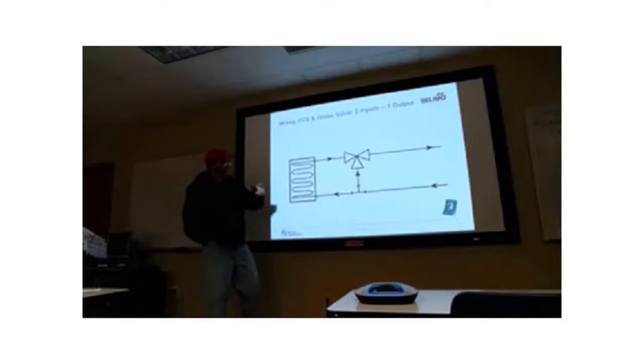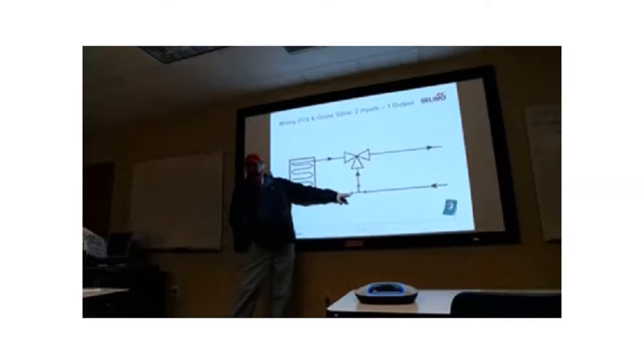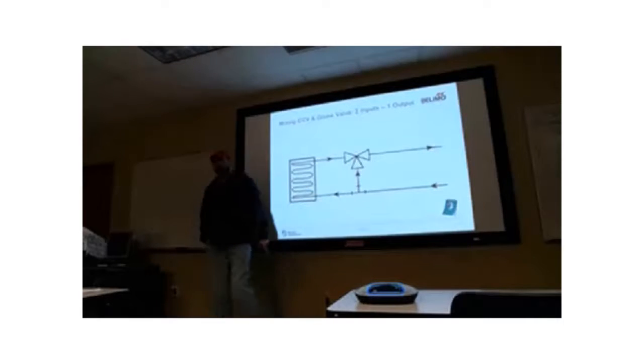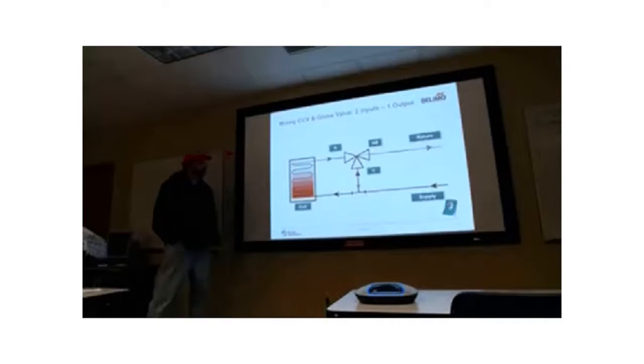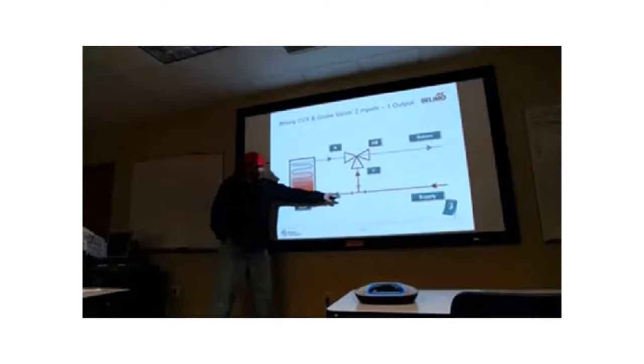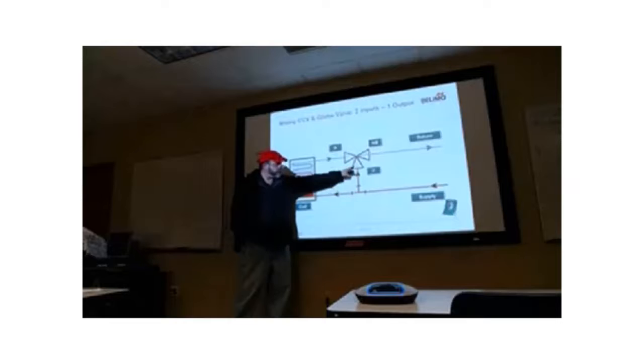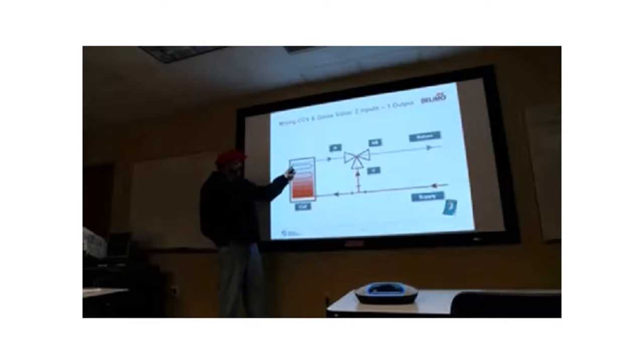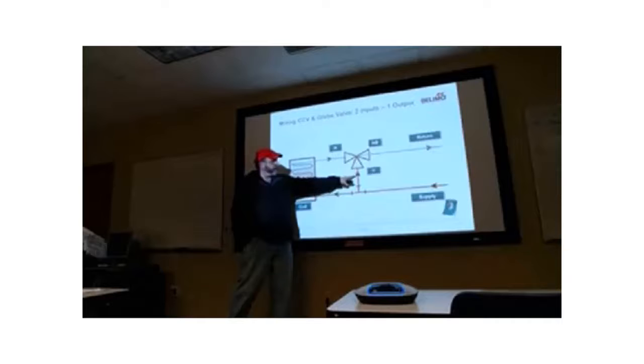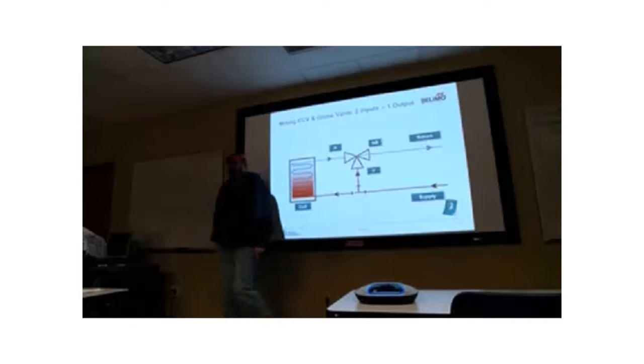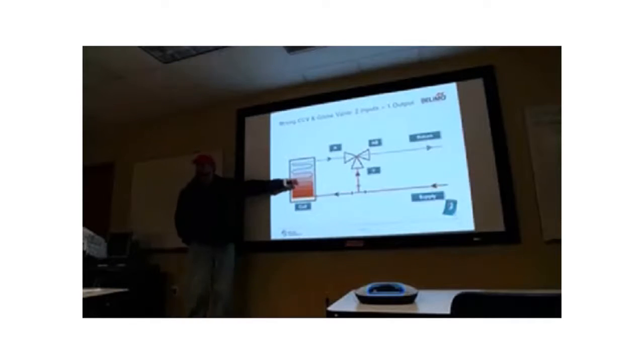If it's on, here's the key. If you find the valve, if the valve is on the supply side and it's a three-way valve, if it's piped correctly, it's a diverting valve, right? Because what it's going to do is divert water around the coil. With the mixing valve, as we see here, you've got water coming through here. This is a heating coil in this case. You've got a bypass, takes the supply from the bypass. The water's through the coil, comes back here and mixes with the supply water and goes back. This does capacity control, right? Because you can control the amount of water that goes through the coil.